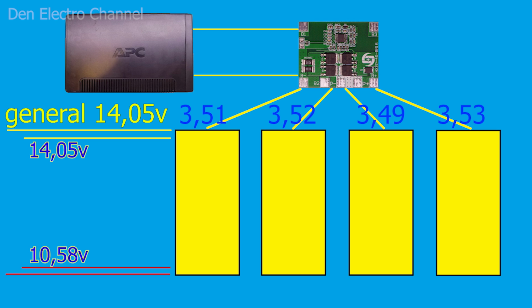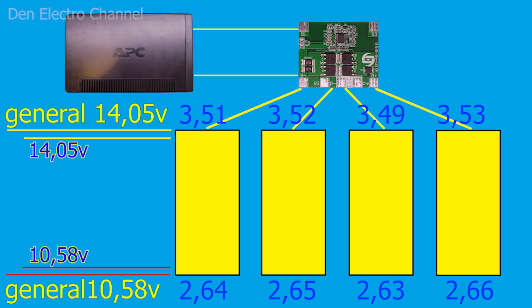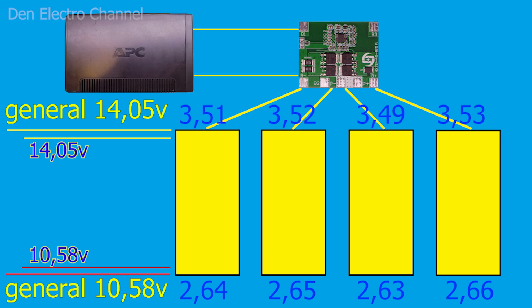The same will happen when the battery is discharged. At this time, the voltage of each cell will be approximately equal. When their total voltage drops to 10.6 volts, the uninterruptible power supply will turn off. In both cases, during charging and discharging, the process will be controlled by the uninterruptible power supply, because its voltage range is narrower than that of the BMS board.